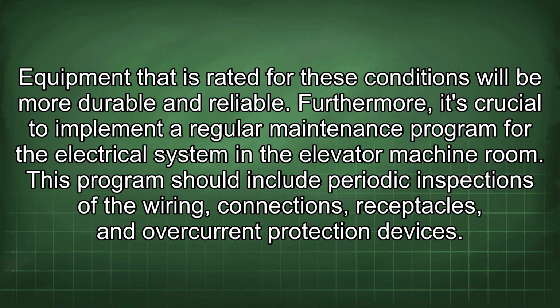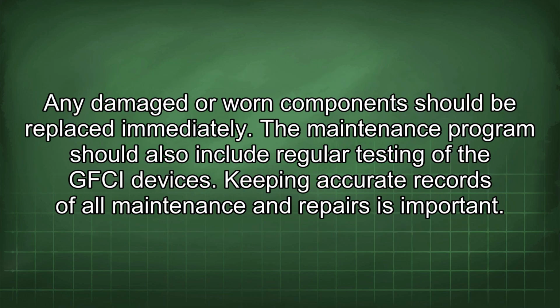Furthermore, it's crucial to implement a regular maintenance program for the electrical system in the elevator machine room. This program should include periodic inspections of the wiring, connections, receptacles, and overcurrent protection devices. Any damaged or worn component should be replaced immediately. The maintenance program should also include regular testing of the GFCI devices.